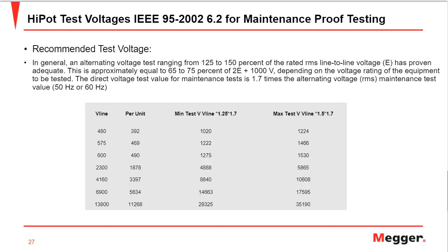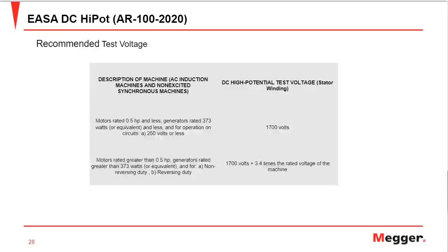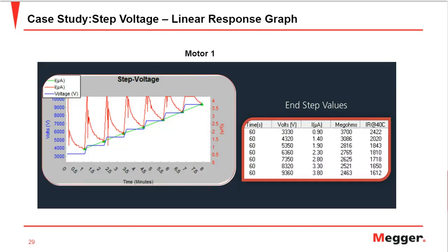And then there is also an EASA DC hypot standard, which is of course a different standard. It tells us if the motor is less than 0.5 HP or less than 250 volts, we use 1700 volts to do a DC hypot test on that motor. If it is more than that, we use the same 1700 volts and add 3.4 times the rated voltage of that machine. So both standards are useful to determine what test voltage we should use in a DC hypot test. We'll see a case study here on two motors, how we can determine the health of the insulation after studying the linearity of the graph. So during the step voltage test, you can evaluate the recorded step leakage current levels for linearity.